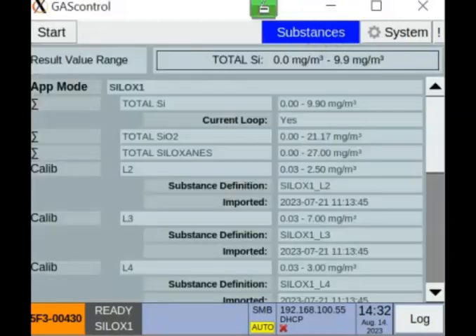Switching to the substances tab allows us to see the result representation, the silicium content, for instance. We have here the application mode. SILOX 1 is one application of the SILOX instrument. We have the total silicium calibration range, the total silicium oxide calibration range, total siloxanes range, and the calibration ranges of the individual siloxanes, which also shows the calibration timestamp, and all individual siloxanes can be looked at individually.